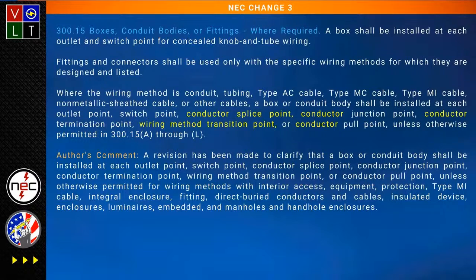I was saying this is one of those transition points where you can actually have access—not where you pull something apart and then claim you've got access at that fitting. That's something Ryan Jackson said, and I said no, that isn't right. They're talking about, like I saw one the other day, a 90 for EMT with a little cover you could unscrew to get access to those wires—almost like an LB in a way. That's what they're talking about here, and this is where they made the clarification. But the main part of this clarification, in my opinion, is the wiring method transition point.